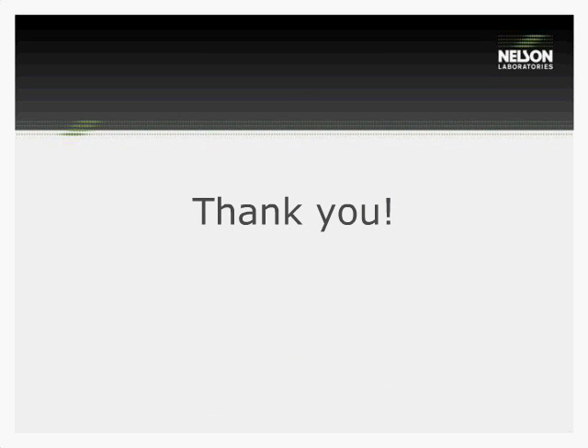Now, in my opinion, the rabbit pyrogen test really isn't a great predictor of pyrogenicity. It takes a lot to cause a response. It's not a test that fails very often. But when you're a reviewer and you're worried about possible pyrogenicity from an ocular contact device, we have seen that kind of thought, that they want to see additional pyrogenicity testing. So even though in this draft document, in my opinion, it doesn't have that, it has a diamond, if I remember correctly, in the chart. So you do have to address it, but it doesn't necessarily mean it has to be done.